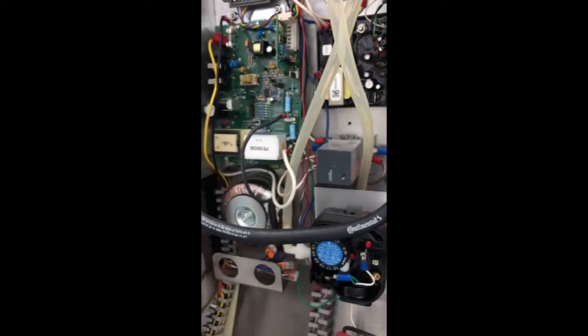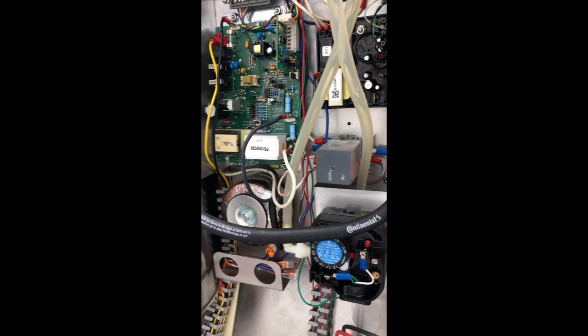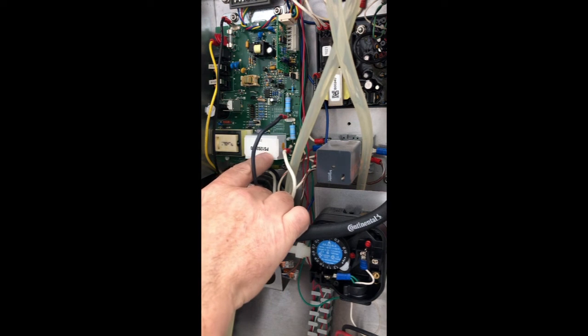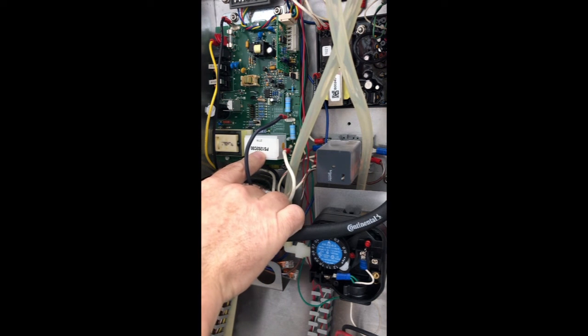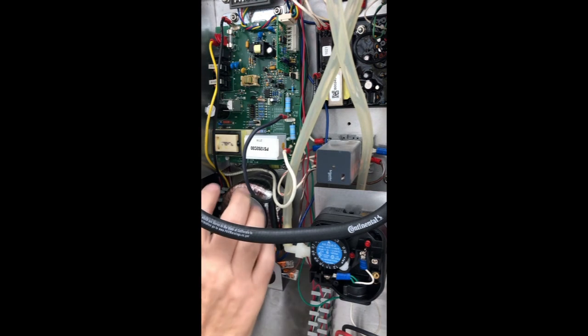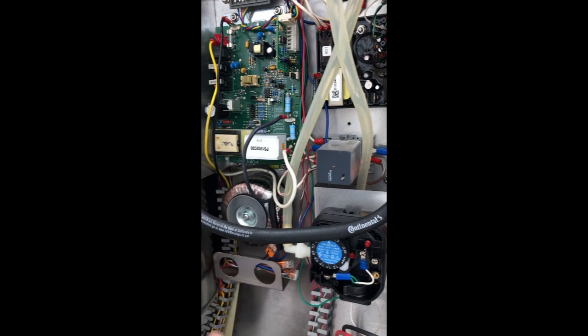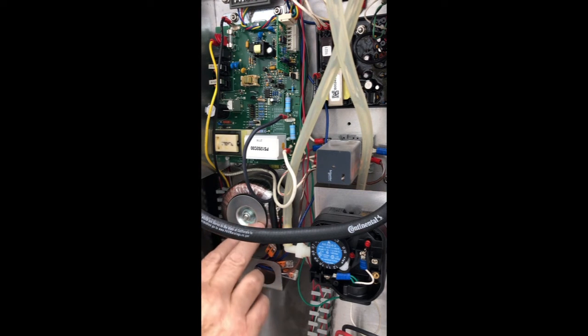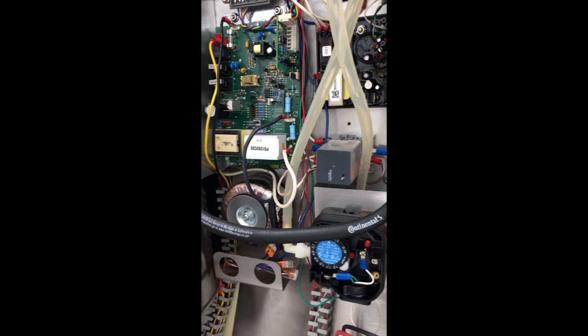But if you have to change out this, or if you have one of these boards that says PS240, that's a 240 volt board. Those will have to be changed out, and you will have to come back and put this transformer in order to make that work. In a lot of cases, if you do not have this set up already, one of the easiest ways to mount this is actually on the old style. There are some holes here, and you can just mount it right into the side of there.